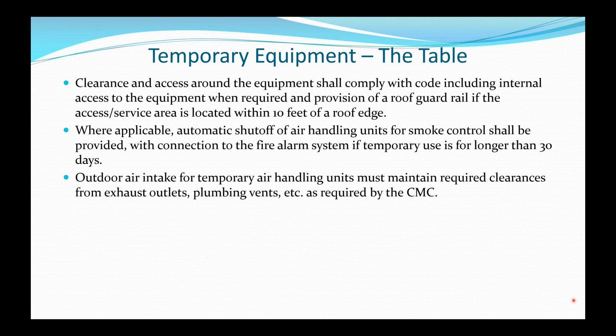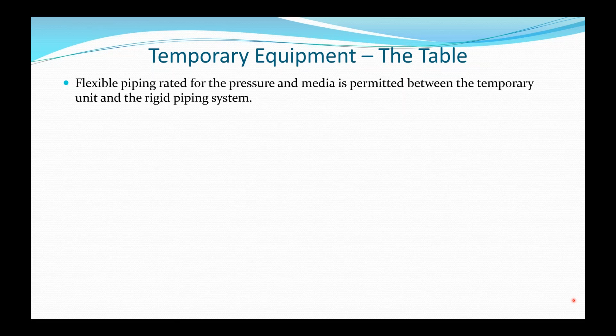And temporary chillers located indoors shall comply with all the requirements of the Mechanical Code, Chapter 11. Okay, if located outdoors, pressure relief shall be located a minimum of 10 feet from the windows or outside air intake locations. Flexible ductwork is permitted between the temporary unit and the hard system. Note that there is no length restriction for flexible ductwork for temporary connections. Same with flexible piping rated for the pressure and media is permitted between temporary unit and the rigid piping system.